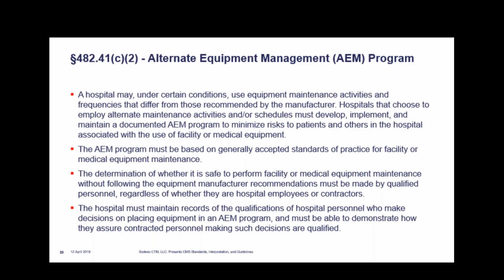So the short answer to your question is no, and the reason for that is liability. Manufacturers create devices and have lawyers that sit in their offices, and they're going to do what they have to do to keep themselves from having any liability. That's why the greatest thing the CMS has ever done for us is given us the ability to do what we do, and the flexibility to go outside of what the manufacturer is suggesting. But I don't believe they would ever be willing to do that, because then they would be saying, I own that responsibility, and you don't have to do it. And with the stuff that's going on with the FDA, it's more likely going to get worse before it gets better.